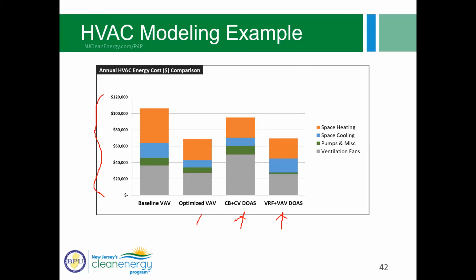Another takeaway, and you might be wondering, oh, the chilled beam didn't do very well. What's going on there? Well, I suspect that this large bit of gray here is because it's a constant volume DOAS. So you're losing out on some savings by delivering a continuous and constant amount of outside air, versus with the VRF with a VAV DOAS, you're getting savings because by using demand controlled ventilation to reduce outside air, you're lowering heating and cooling loads, and you're also getting fan energy savings. So it would have been also interesting to look at how this option here would have compared with an option with chilled beam, but with a variable air volume DOAS. So that would have been interesting.